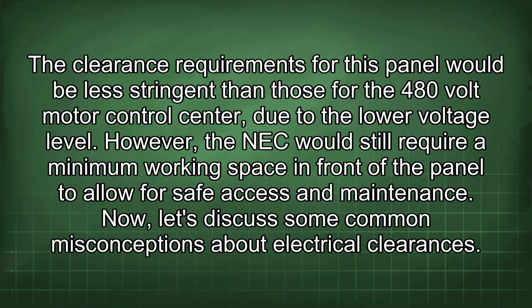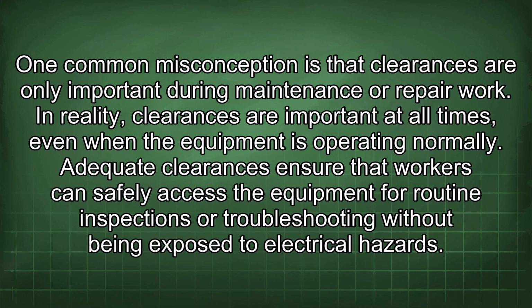Now let's discuss some common misconceptions about electrical clearances. One common misconception is that clearances are only important during maintenance or repair work. In reality, clearances are important at all times, even when the equipment is operating normally. Adequate clearances ensure that workers can safely access the equipment for routine inspections or troubleshooting without being exposed to electrical hazards.